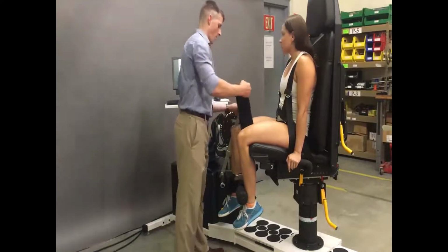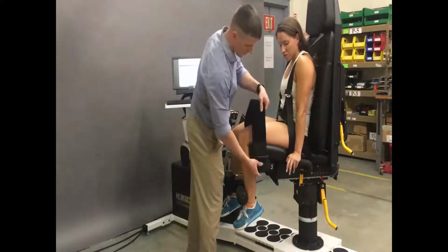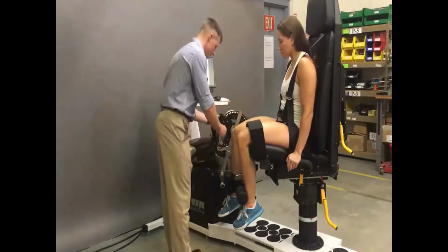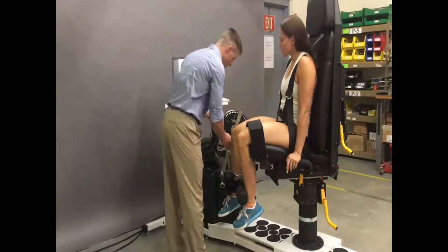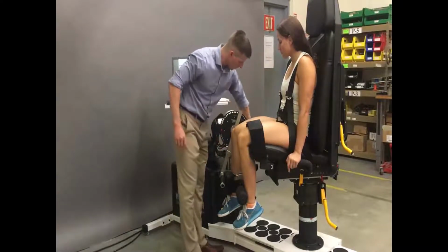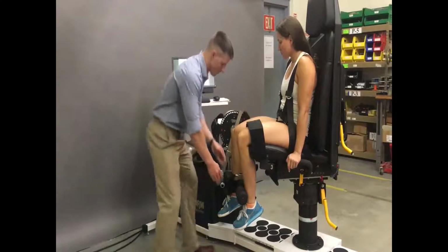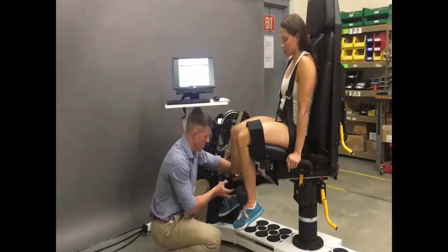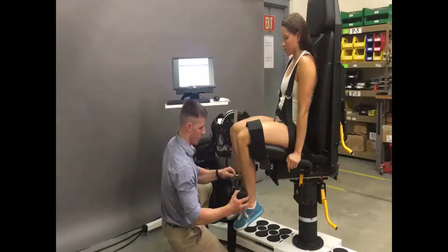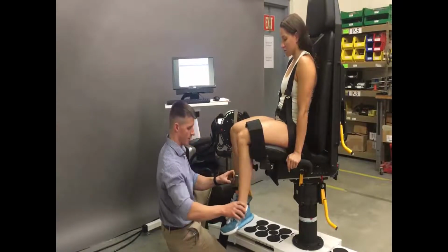So now we're just going to turn the whole chair assembly so we can test the other leg. Now she doesn't have to move at all. First thing to do, go ahead on the software, tell it the other limb, that unlocks the adapter. Now you can move the thigh strap, you can unhook the adapter from the leg, and you can move that contralateral limb stabilizer.